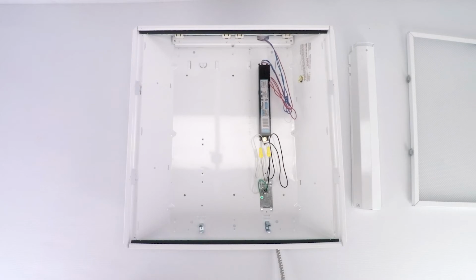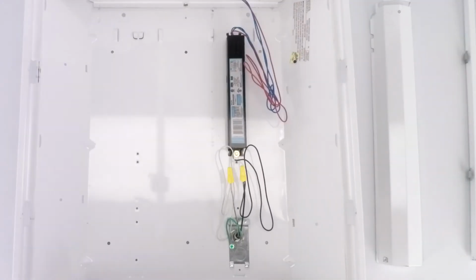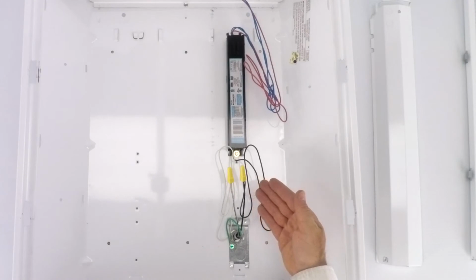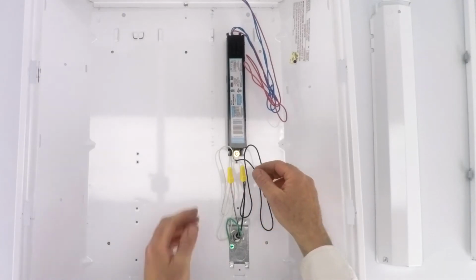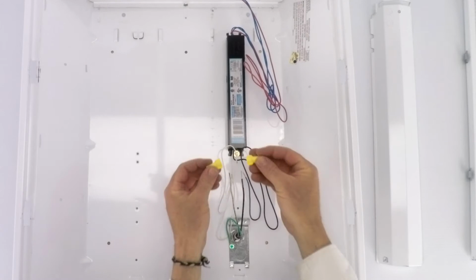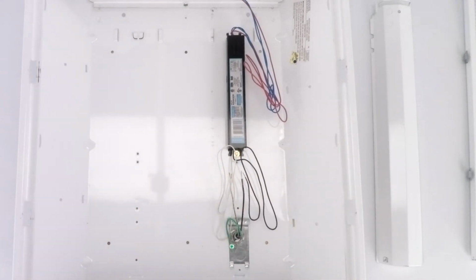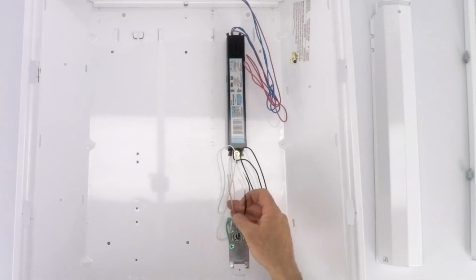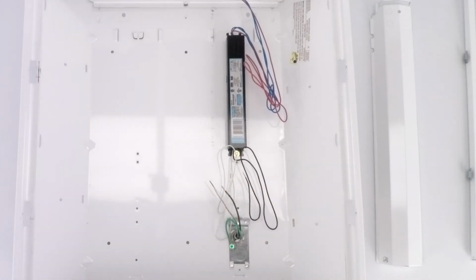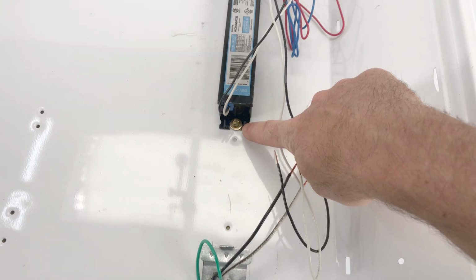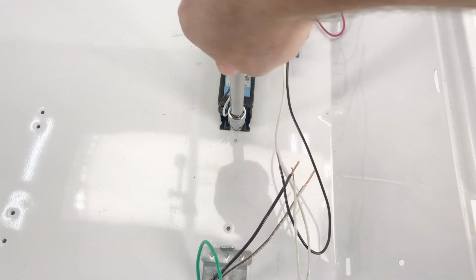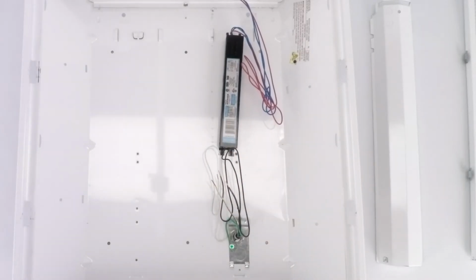Well, the first thing we want to look at is, where does the power come in the light fixture? And if there's wire nuts on your white and black, and the power's off, you can take your wire nuts off now and pull those away. And the next thing we need to look at is, we're going to replace all the ballast and all the wiring. So it's all going to come out. To take the ballast out, there's a nut on one end. If you take the nut off and slide the transformer away from the housing, it'll come off in your hand.